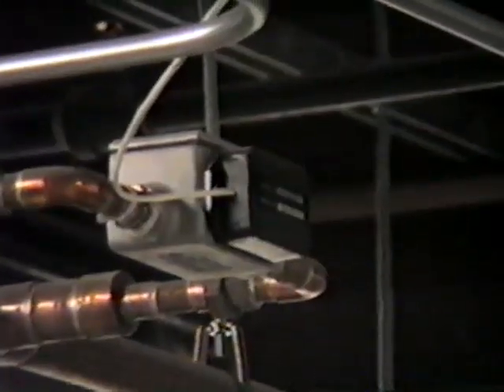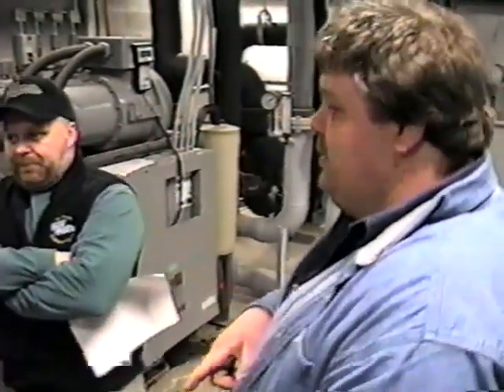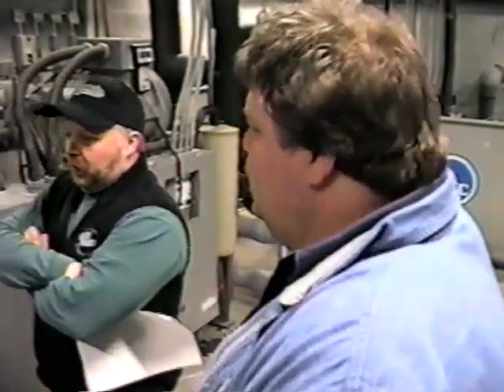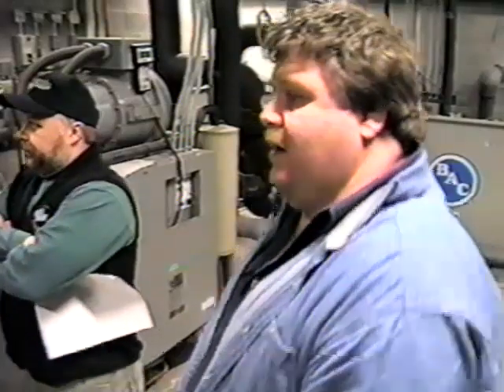I would never recommend in an alarm condition that one person enter the room. Always work in pairs. Right. So get one guy at the door, use the buddy system, and it's the type of room where you can take one breath and get in and get out. But you're better off in that case calling somebody that deals with refrigerant all the time, just for liability purposes, everybody.